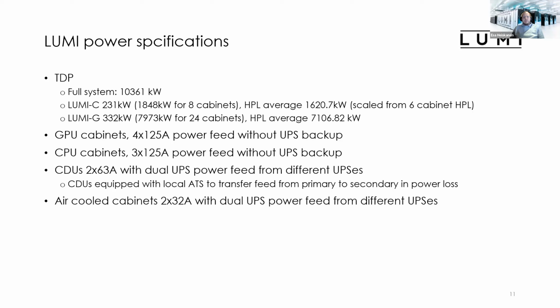In the HPL average, which we ran when the Lumi CPU partition was installed, we then had 6 cabinets installed, and our HPL power average was 1.2 megawatts. So this is scaled up from that number.